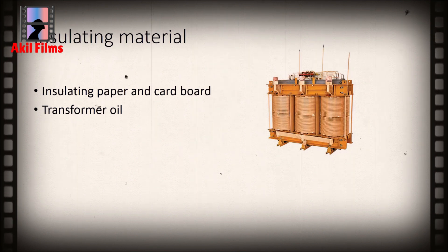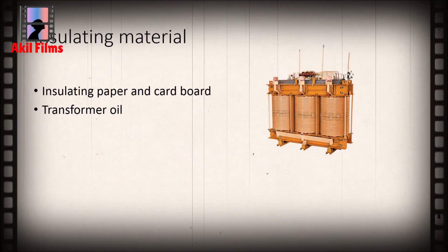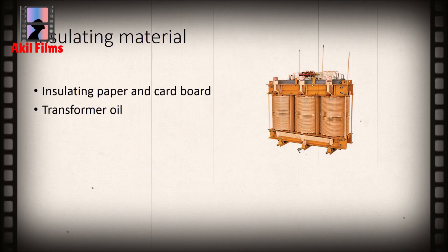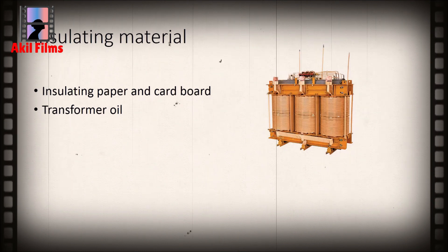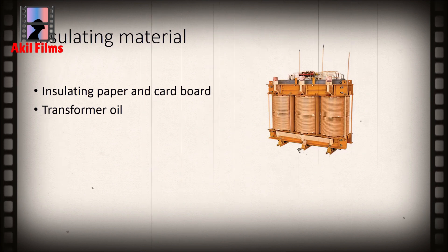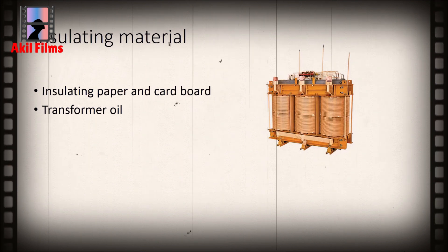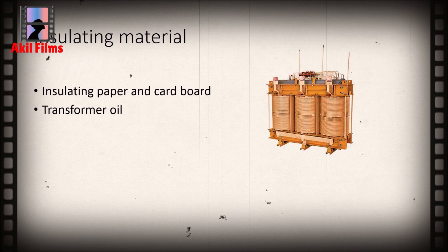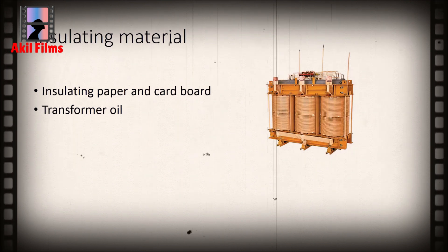Transformer oil is another insulating material. Transformer oil performs two important functions: in addition to its insulating function, it can also cool the core and coil assembly. The transformer's core and winding must be completely immersed in the oil.